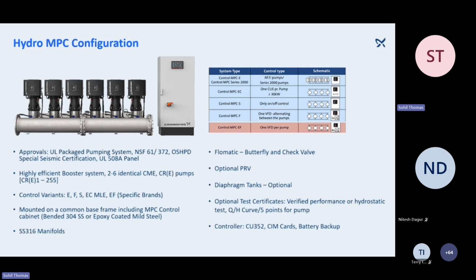So this is a Hydro MPC multi-pump controller configuration, which comes pre-wired and pre-tested from the factory, with an advanced Genicon controller. This is an NSF 61 372 approved system, and you can go from 2 to 6 identical CME or CRE systems. It comes with SS316 manifolds, as a complete package system where you can just install it, and the contractor finds it very easy to install and commission at site. So you're saving a lot of time, and at the same time you're getting a complete system from Grundfos, which is highly efficient, with lower energy consumption as well.